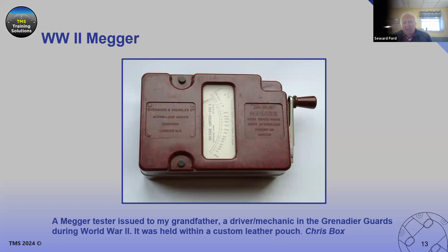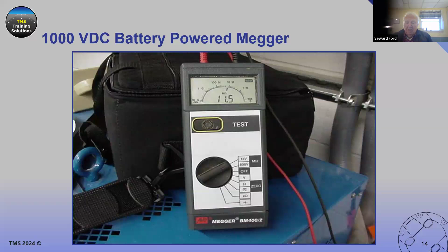The next slide shows a more common 1,000-volt DC battery powered megger. This is the one that a lot of you at the airport should have, and if you don't have it, you should. This allows you to put 1,000 volts DC out on a segment of the circuit or the whole circuit. When we think we have a problem in a particular area, we can isolate that area, measure that part of the circuit, and see what our reading is. Then we might measure the adjacent segment and find that it's normal in our estimation. So we can isolate and find where a problem is by measuring particular circuit segments, or we measure the whole circuit, which is quite often the case.